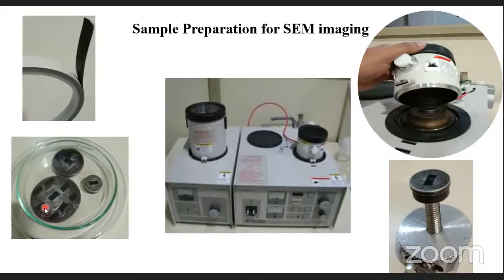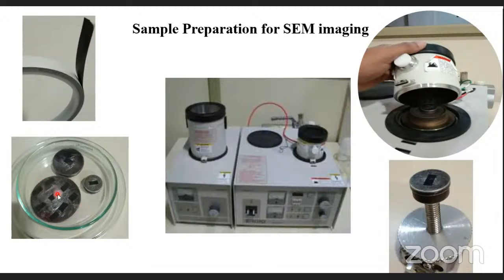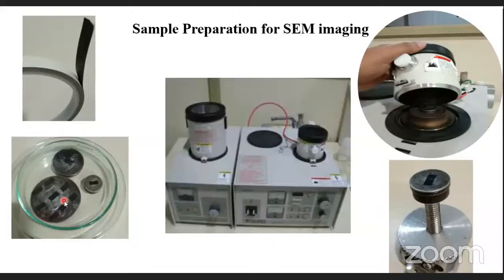The stub design depends on the instrument company, but for our instrument the advantage is that multiple samples can be analyzed in a single stub — around 10 to 12 small samples can be placed together. For powders, you can put a very small pinch of powder directly over the stub. If the sample is conductive, you can put it directly into the machine without any coating. If it is non-conductive, like polymers or biological samples, we use the gold sputtering unit.